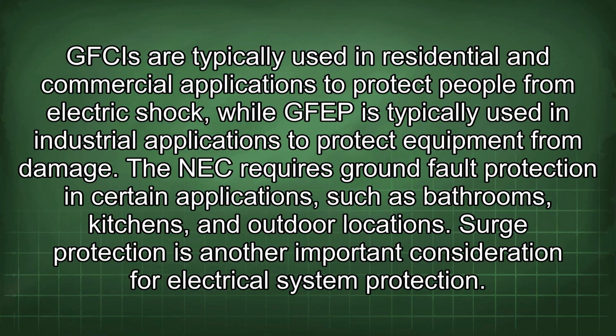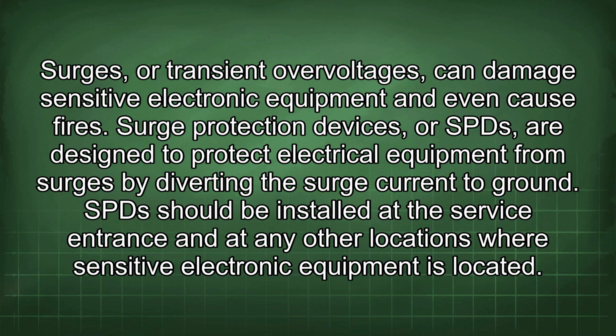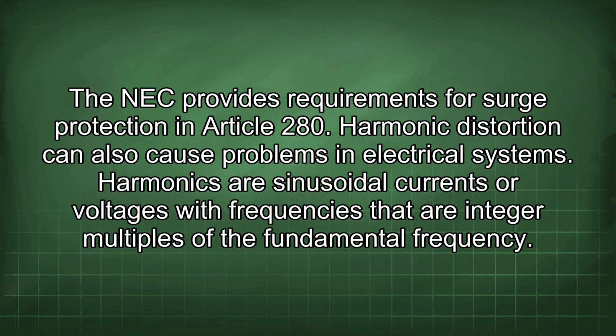Surge protection is another important consideration for electrical system protection. Surges, or transient overvoltages, can damage sensitive electronic equipment and even cause fires. Surge protection devices, or SPDs, are designed to protect electrical equipment from surges by diverting the surge current to ground. SPDs should be installed at the service entrance and at any other locations where sensitive electronic equipment is located. The NEC provides requirements for surge protection in Article 280.